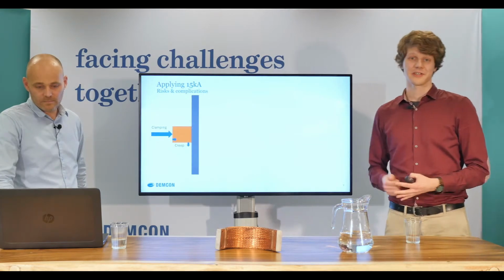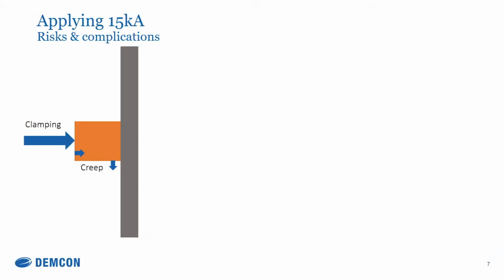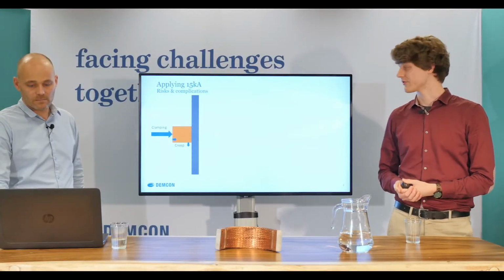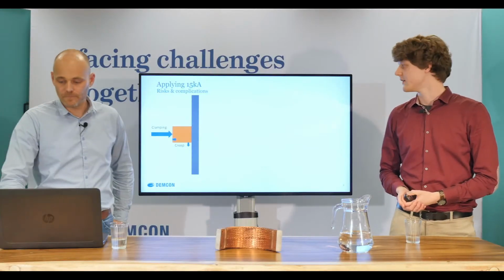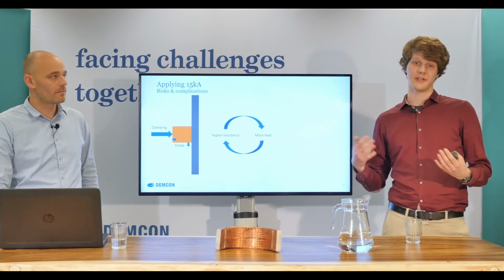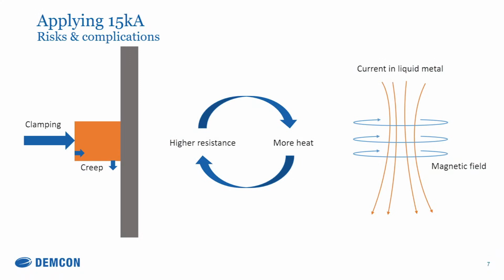Some further risks and complications involve, for example, clamping the copper onto the tubing. When copper reaches a higher temperature and approaches the melting temperature, it actually starts to creep away from the clamping force. So if this copper gets too hot, the clamping mechanism will simply stop working, which is a risk in our test setup. In addition, when copper heats up, the electrical resistance increases, and because we apply such a huge current, the heat generated in this copper also increases in turn, and that keeps going in a cycle.